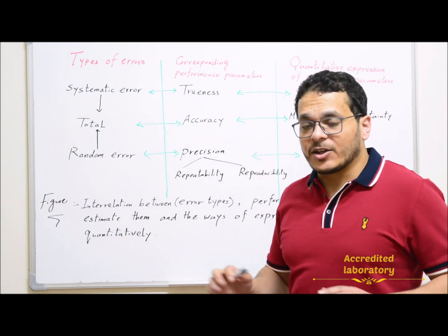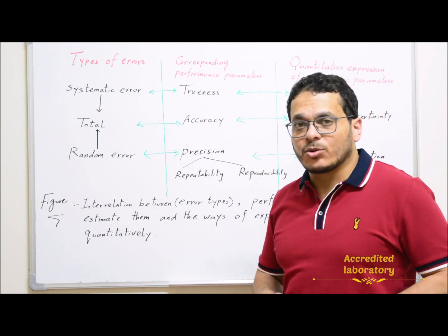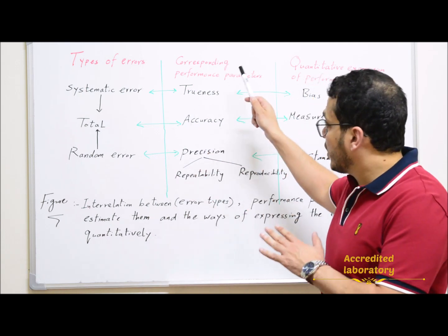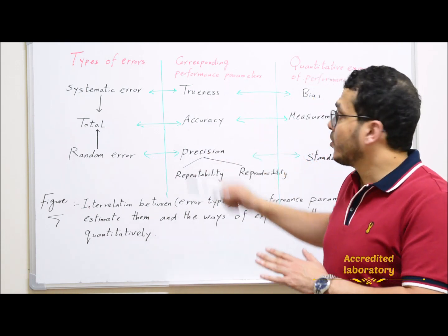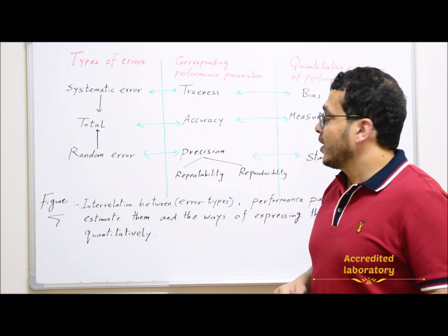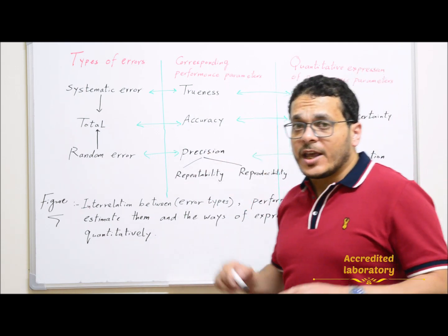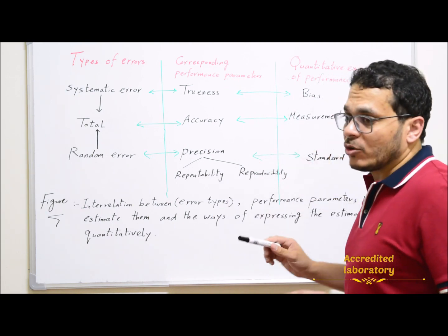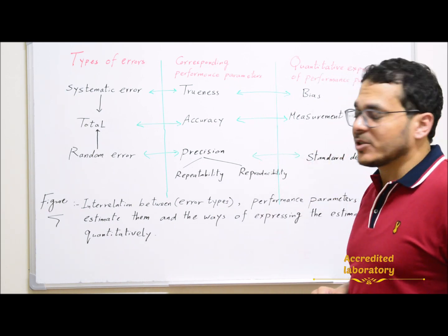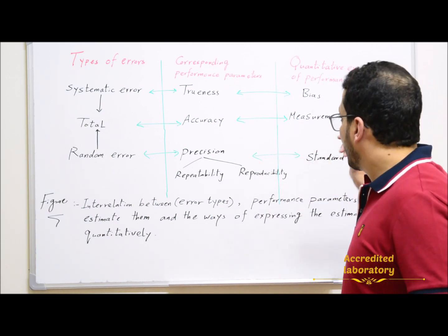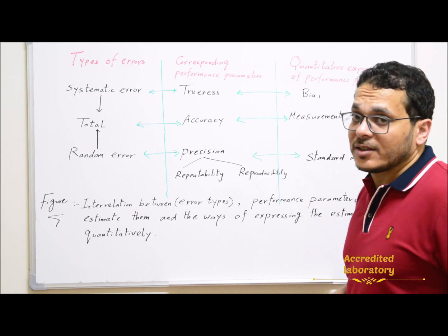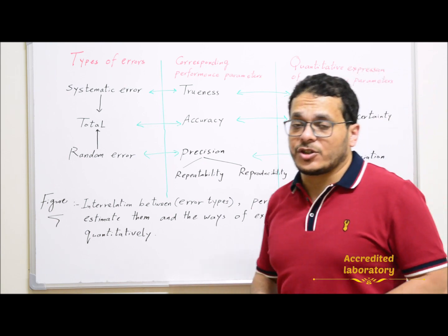Let's look at the interrelations between types of errors — systematic, random, and total errors — and their corresponding performance parameters: trueness, accuracy, and precision. The quantitative expressions of these performance parameters are bias, measurement uncertainty, and standard deviation, respectively.